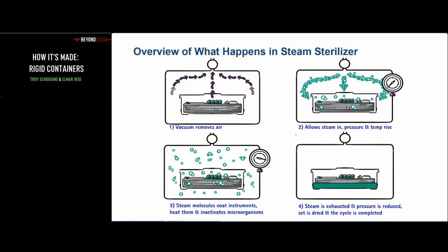So the first step is that basically the air is removed from the sterilizer. The vacuum removes the air, and then the heat and pressure rise in there as steam comes in. That helps create steam, and the steam molecules will coat the instruments themselves, kind of in the third phase there, and inactivate any of the microorganisms. So that will allow everything to be killed. And then basically it will go through an exhausting phase and then a drying phase.